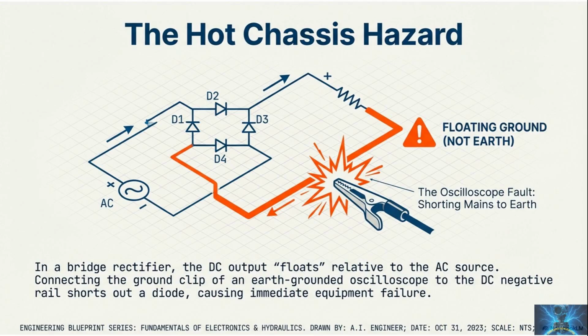The hot chassis hazard, floating output and oscilloscope mistakes. A bridge rectifier output floats relative to the alternating current source. Floating means the direct current negative is not automatically earth ground. An earth-grounded oscilloscope has a ground clip tied to earth. If you clamp that ground lead onto the wrong spot, you can accidentally short part of the bridge to earth and blow a diode instantly. The safe habit is to verify what is earth referenced, use isolation when needed, and think before you clip.